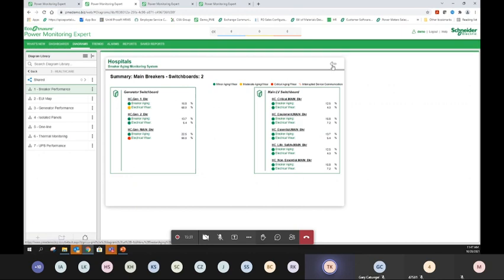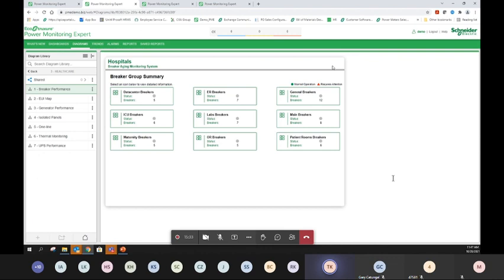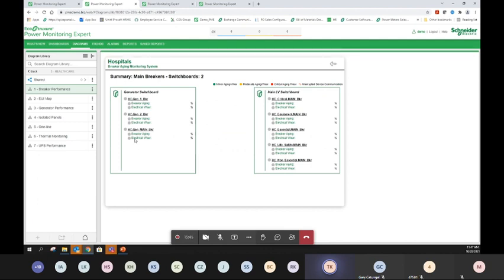So how does this help your maintenance, predictive maintenance, proactive maintenance? You can see here this breaker, for example. The moment that you go into this breaker, you will see the electrical wear. So the software is measuring the mechanical and electrical wear. So in that case, for example, let's say you have a maintenance shutdown on the switchboard 1 area in coming December, for example.